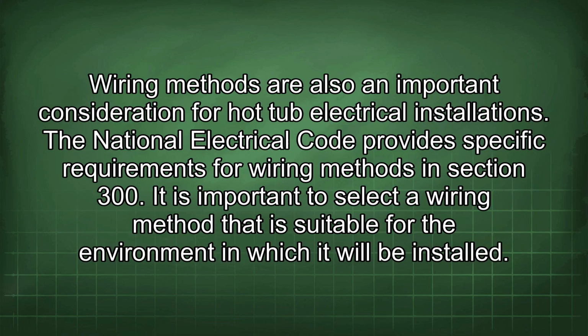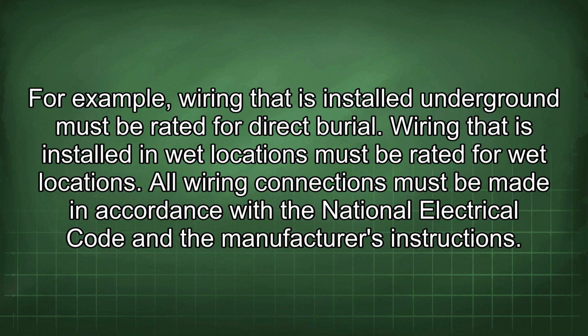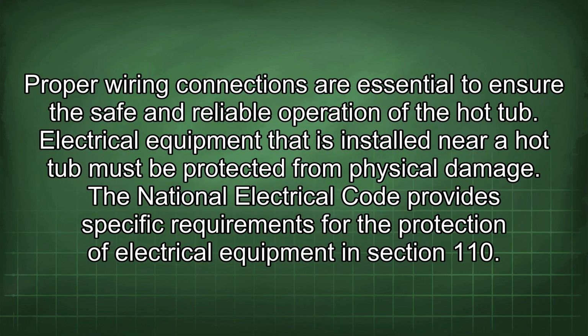Wiring methods are also an important consideration for hot tub electrical installations. The National Electrical Code provides specific requirements for wiring methods in Section 300. It is important to select a wiring method that is suitable for the environment in which it will be installed. For example, wiring that is installed underground must be rated for direct burial. Wiring that is installed in wet locations must be rated for wet locations. All wiring connections must be made in accordance with the National Electrical Code and the manufacturer's instructions. Proper wiring connections are essential to ensure the safe and reliable operation of the hot tub.